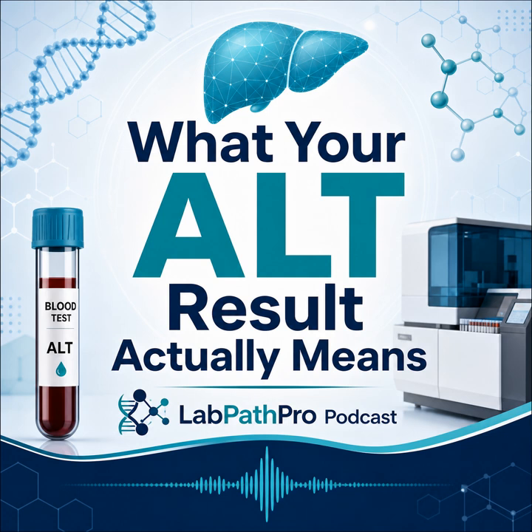And following calibration is internal quality control, or IQC. This is where they run fake samples with a known exact amount of ALT to see if the machine hits the target, right? Yes, and labs apply strict statistical frameworks to this, known as Westgard rules. Sounds intense. They are. They rely on standard deviations from the mean. So if a quality control sample reads outside of these highly specific statistical boundaries, say, it's consistently reading a little too high over several days, it flags an error. And then what? The cardinal rule of any accredited laboratory is that a patient result must never be released if the quality control has failed.